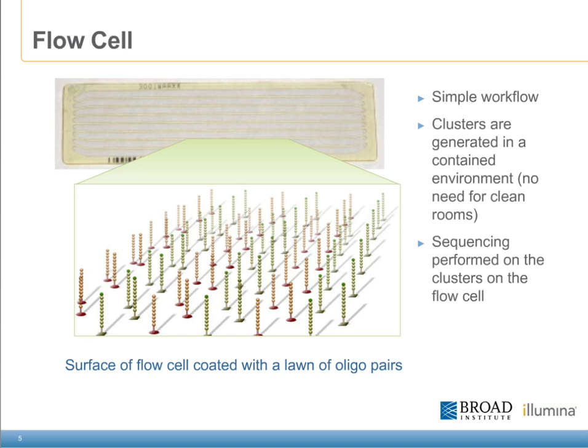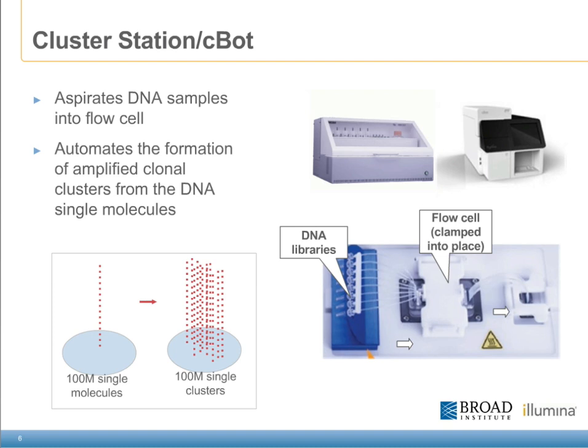The inside of each lane is coated with a gel matrix, which we cross-linked our unique adapters to that will complement the oligos on your library. In this way, we're able to generate the clusters in a contained environment and treat multiple samples at once within the confines of the flow cell. The cluster station and C-Bot are the two devices for cluster generation at Illumina. The C-Bot is the latest incarnation, and it vastly simplifies the number of hands-on user steps required to generate clusters.